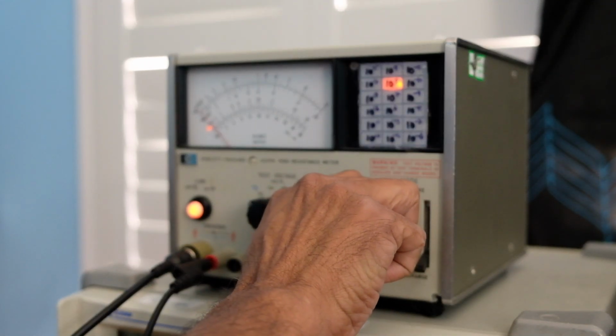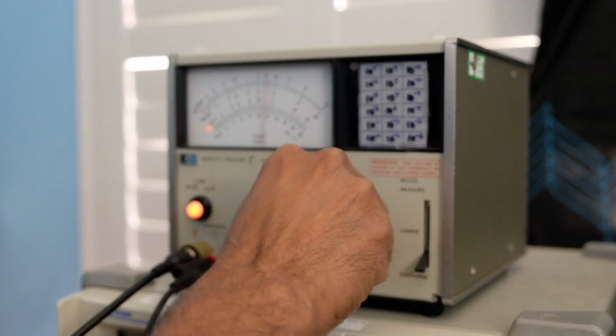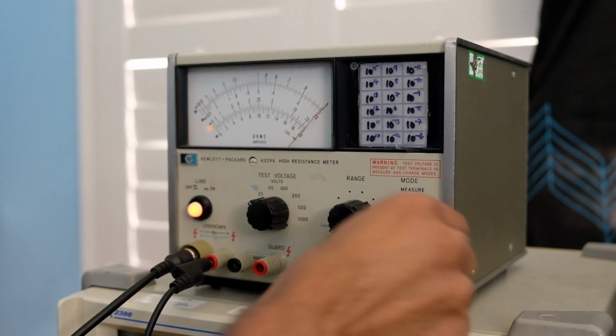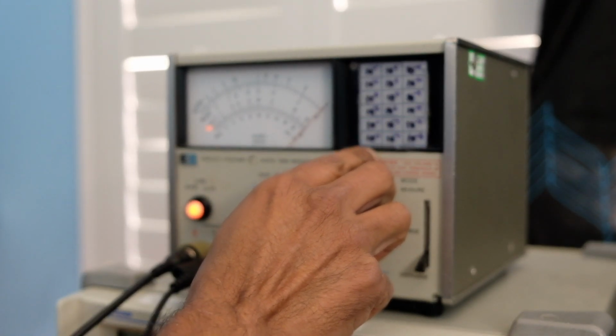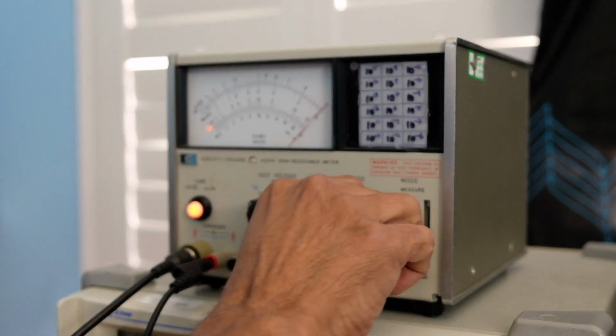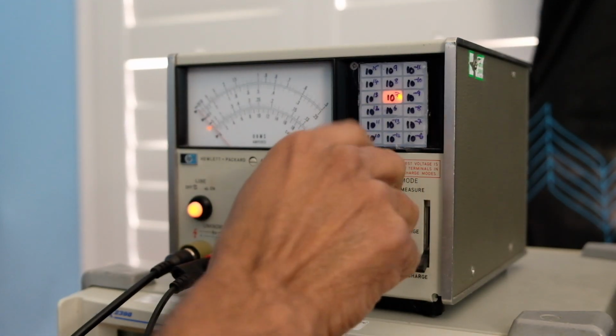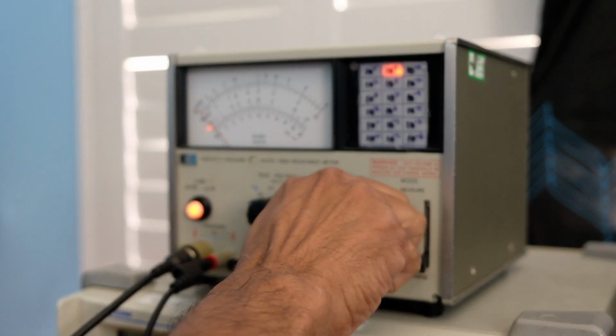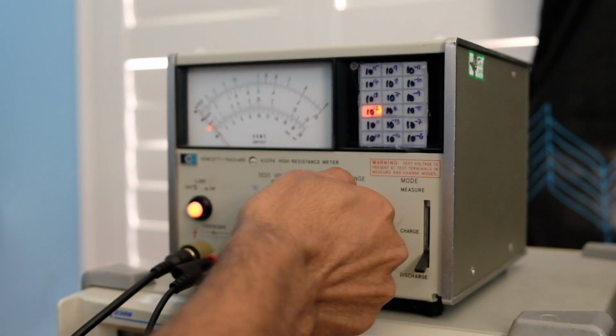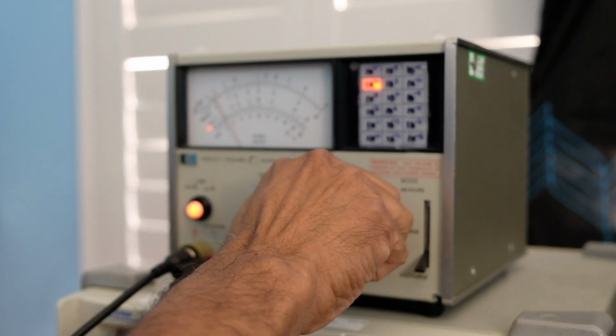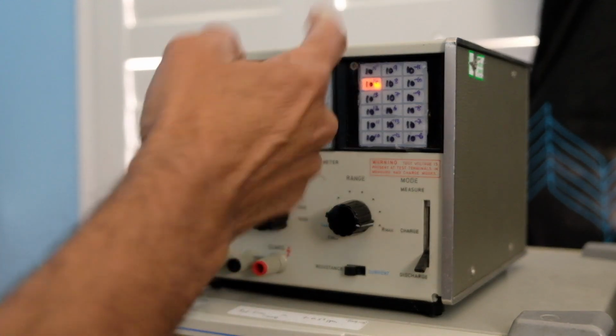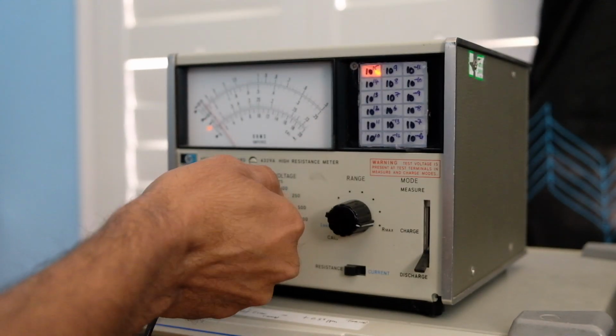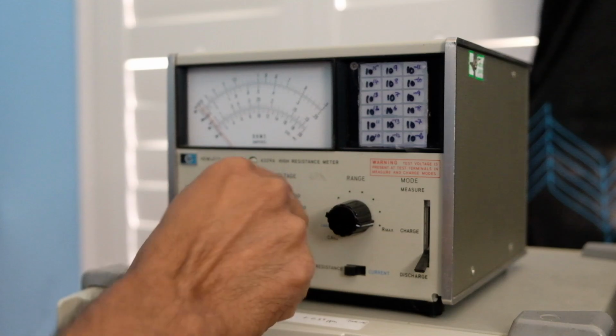As you can see, I'll switch through the ranges to show you. The minimum it can go is 10 to the 6 ohms full scale, then 10 to the 7, 8, 9, 10, 11, 12, 13, 14 and 10 to the power 15. If you go to the higher ranges, you'll see the 10 to the power 15 will actually light up. It's the higher test voltage settings.